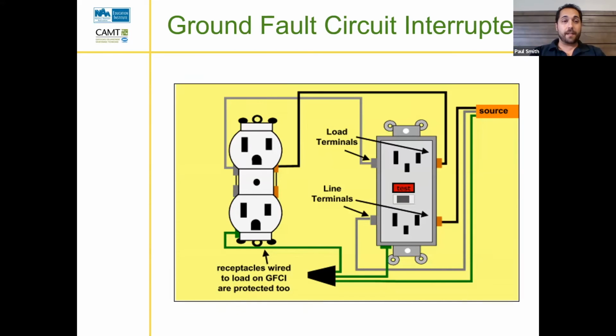With the test and reset button? Correct. So if we hit test and reset, what happens if it doesn't reset? It's bad. Or there could be another reason it doesn't reset: lack of power. Yeah. So that's the two things to troubleshoot it.